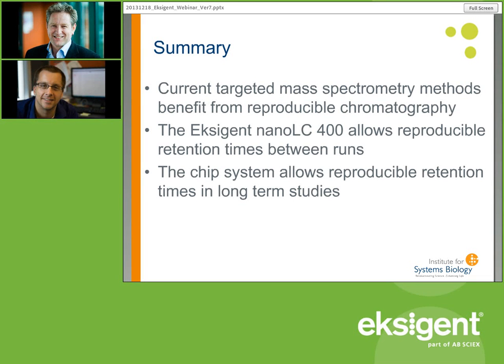Another question: how much protein do you typically inject for a complex sample, and how much less material would you inject by nanoLC versus conventional UPLC with a 2.1 millimeter column? What I usually aim for is about one microgram, and often go less — say 0.5 to one microgram for the nanoLC. For columns with a bigger diameter, you want to go higher, and you can analyze up to 20 micrograms using a 2.1 millimeter column.